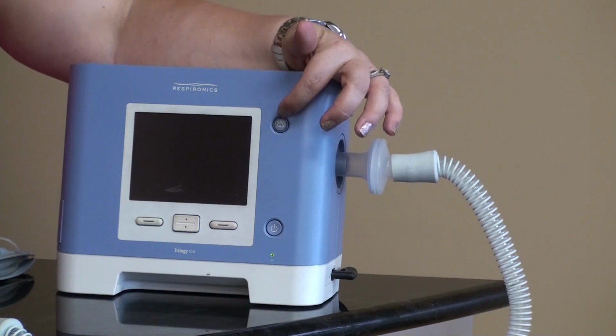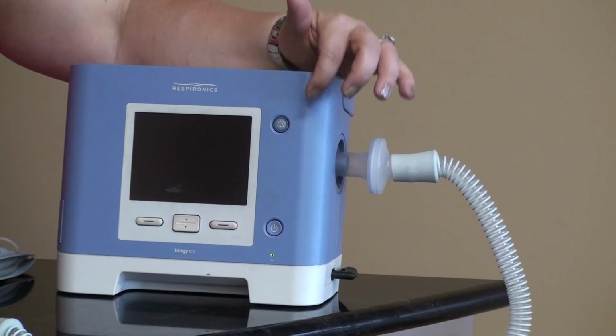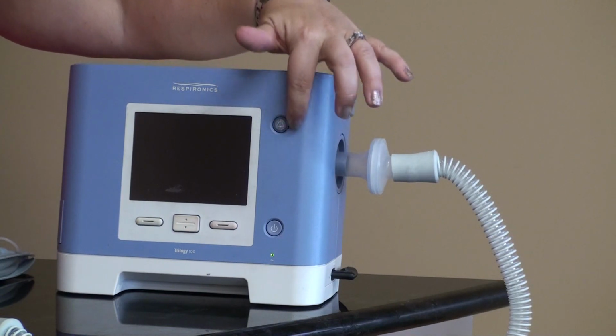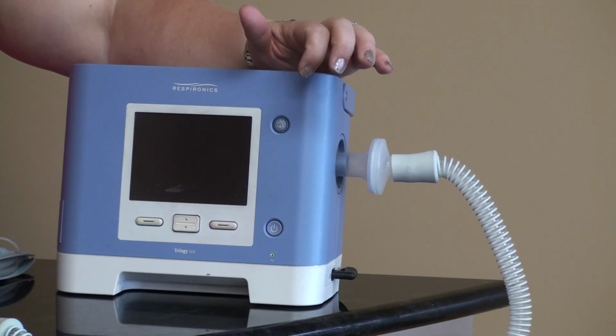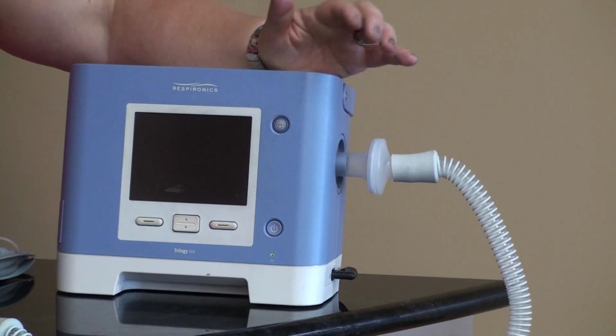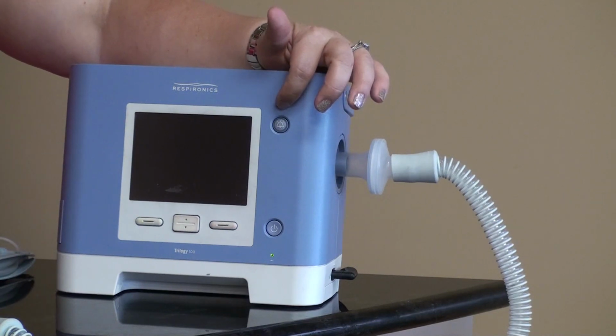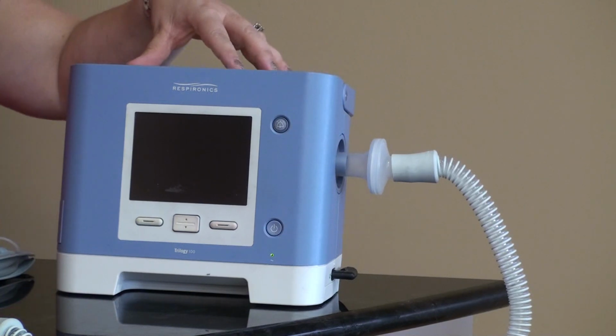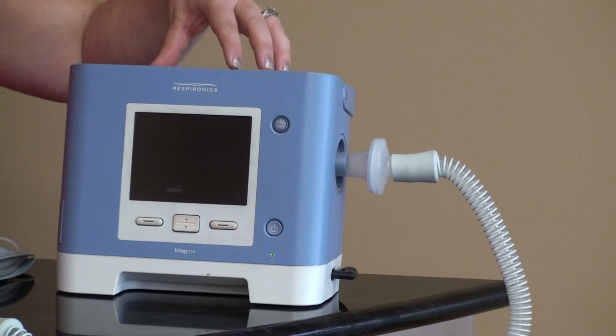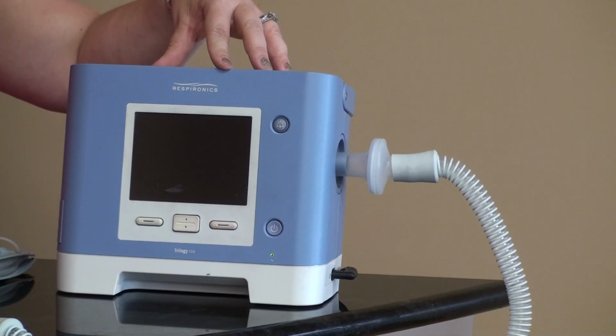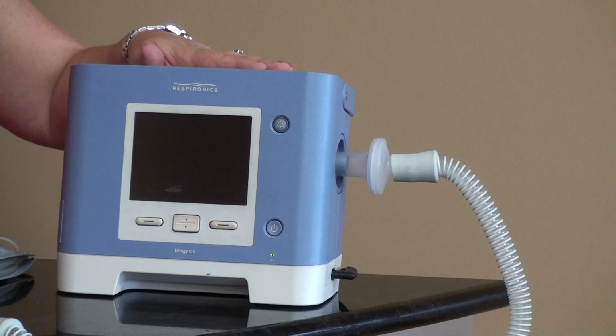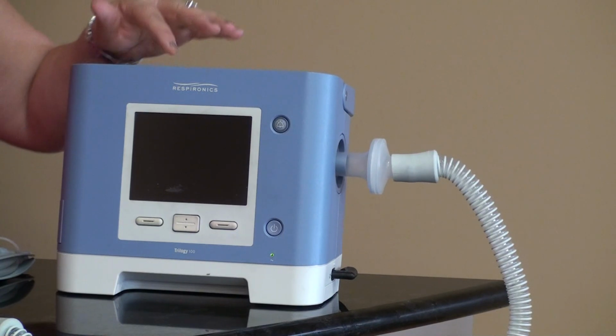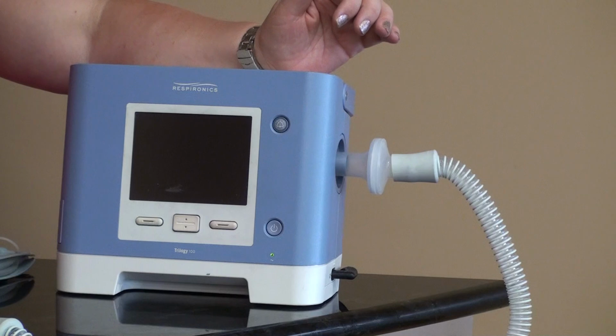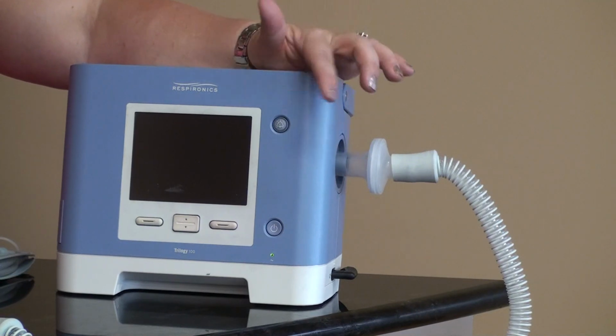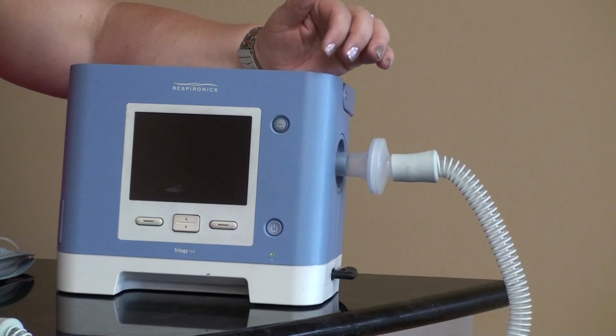D is going to be your red alarm LED and audio pause button, which is this button up here. Okay, it's a dual purpose. You can pause your button here for your alarms. It also lights up around here. And when we actually turn it on, I'll show you some differences in the alarms. This technology is very, very smart on this particular ventilator. It determines whether your alarms are low priority, high priority, or moderate priority by looking different and sounding different. And we'll go over that a little bit further down the line. When you hit this silence, it'll silence it for up to 60 seconds or 1 minute, and then it'll go ahead and be activated once again.